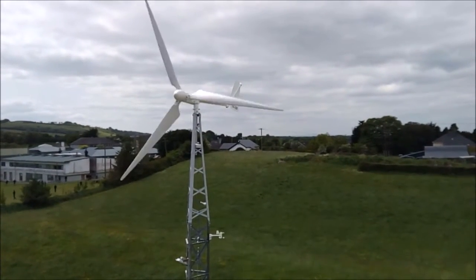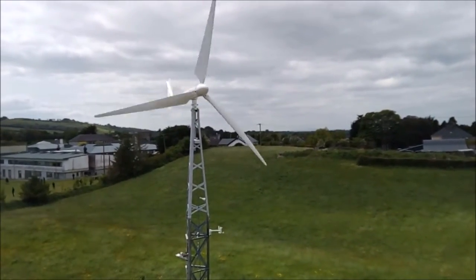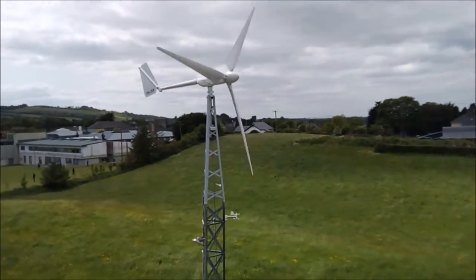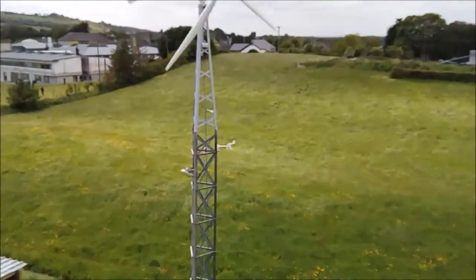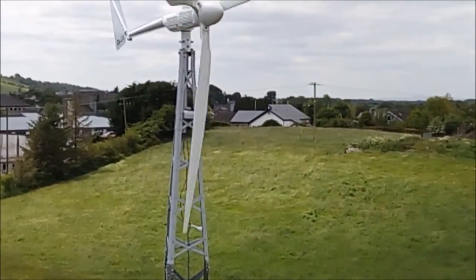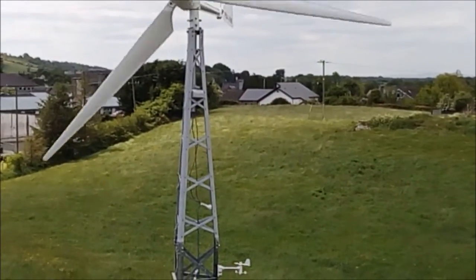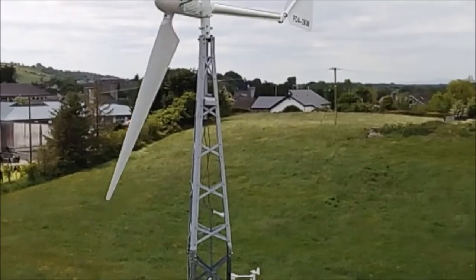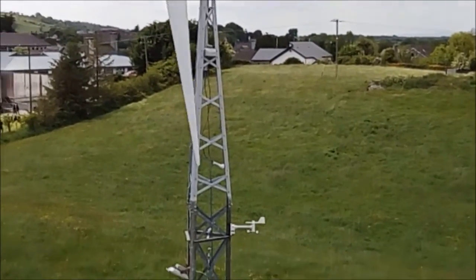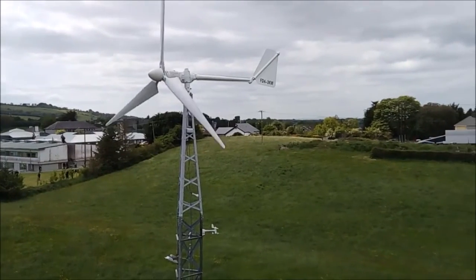It's not running efficiently — the cables are very inefficient now. The cables are way too small at the end. The big cable — the 3 cables sort of in the middle — there are three 10-square cables. I don't know what that is in American Wire Gauge, but underneath there's 4-square, so it's very inefficient for carrying current.